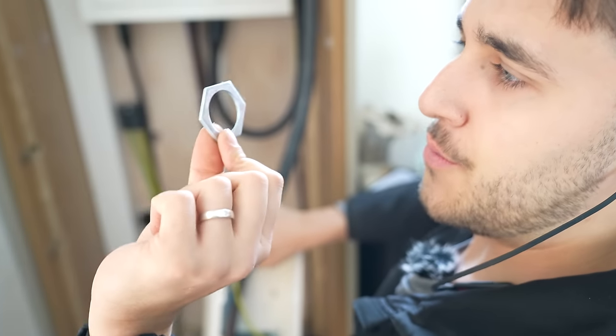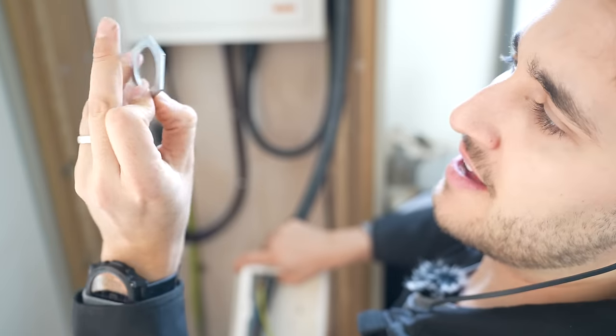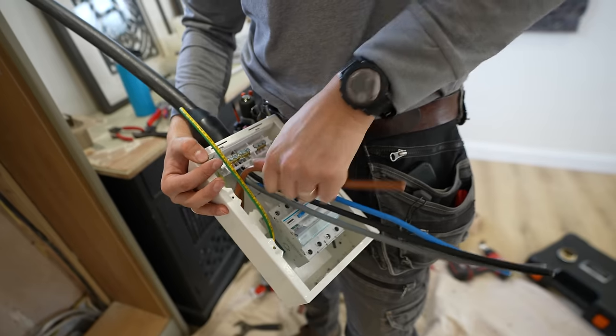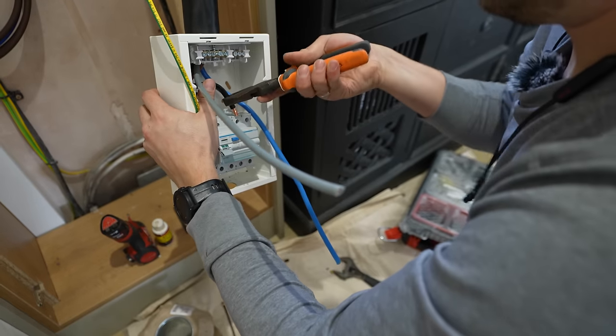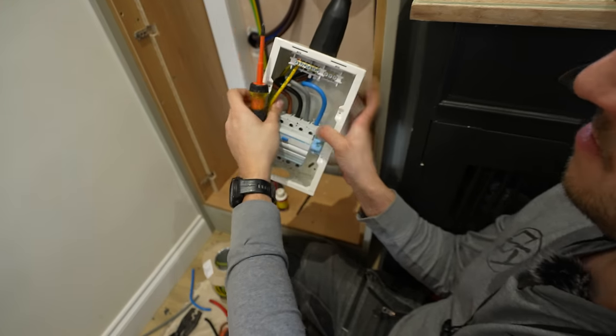Steel wire armoured cable — it's fantastic stuff. I say that because it has lasted the test of time. I'll be working in buildings that have got this cable still operating after 50 to 60 odd years and it's still working absolutely fine. Armoured cable, when done right, will outlive you. Also note there is a right and wrong way to fit the lock ring — the rounded edge wants to be facing the gland, and the flat edge wants to be the bit actually touching it.